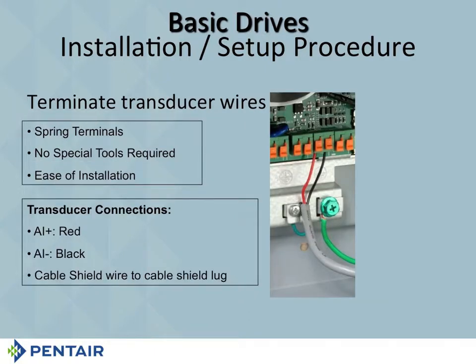When you're doing your transducer, AI plus is going to be red, AI minus is going to be black. Those are spring loaded, so you can just push them up with your fingertip if you want. A screwdriver gives you a little more room to see with, but you just push them up, stick the wire in. Now, the other thing I'm going to mention to you is make sure that you strip enough wire off so that when you push that wire up in there, you're not on the coating of the wire. Because obviously, if you're on the coating of the wire, that coating is an insulator, and you're not going to sense anything. So you make sure that wire is stripped back far enough. When you put it up in there, you're on the stripped wire. The other thing that's very important is there is a 3rd wire in there. It is a shield cable. And you want to hook that up to the shield cable lug.